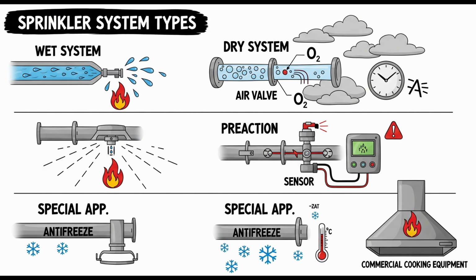It's permitted for use with ESFR sprinklers if those specific ESFR sprinklers are listed for that application with that solution. The ESFR exception again. If the sprinkler and the specific propylene glycol are tested and listed together, it's allowed. Correct. It's a specific carve-out for that combination, if proven safe and effective through listing.